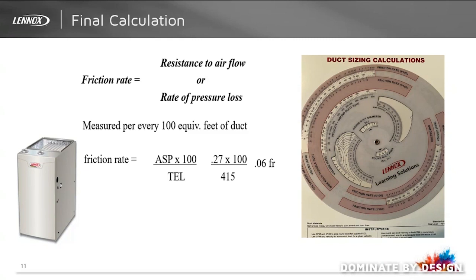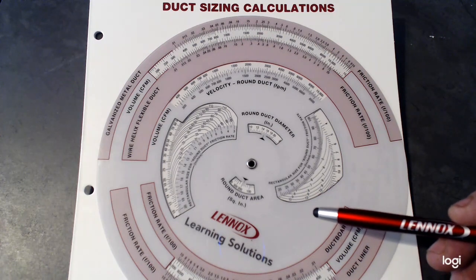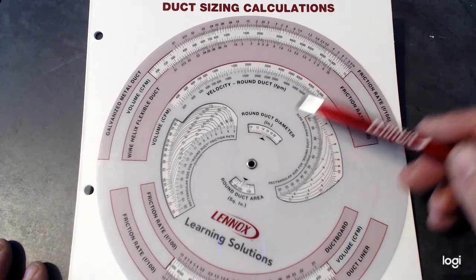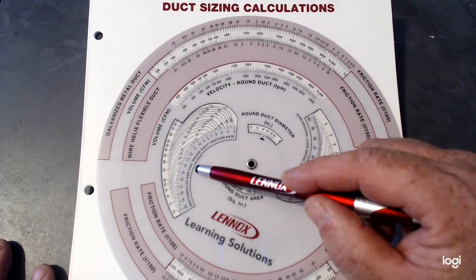This 0.06 friction rate is the number we are now going to use in our duct calculator for sizing metal duct and flex duct for both supply and return. Here we have the duct calculator provided to us by Lennox Learning Solutions. What's unique about this duct calculator is that it has the friction rate for metal duct as well as the friction rate listed for flexible duct. There are also other calculators available — rectangular ones and apps on cell phones — to accomplish the same thing. The volume in CFM is shown in the middle, and the calculator also includes equivalent lengths for fittings. For today's exercise, we're going to focus on the friction rate number and the round duct diameter section as well as the square and rectangular duct section.